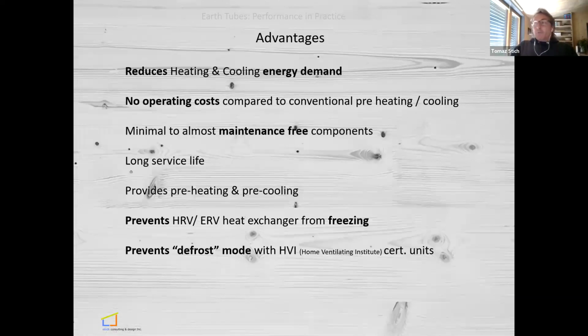So when we installed our earth tube, we didn't use that one. We didn't use anything. I wanted it, so we did it. And it turns out to be very cost effective and practical. So the advantages of an earth tube: it reduces heating and cooling energy demand. Operating costs are zero. They are pretty much maintenance free, except cleaning every, I would say, 10 years. It provides preheating and pre-cooling, and it prevents the heat exchanger from freezing in winter.